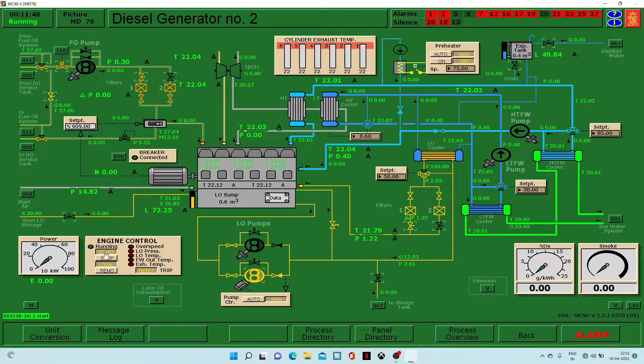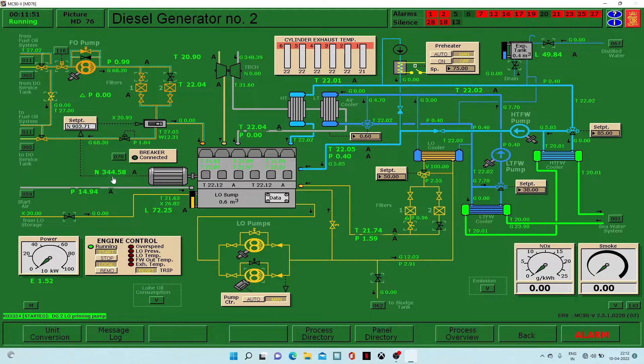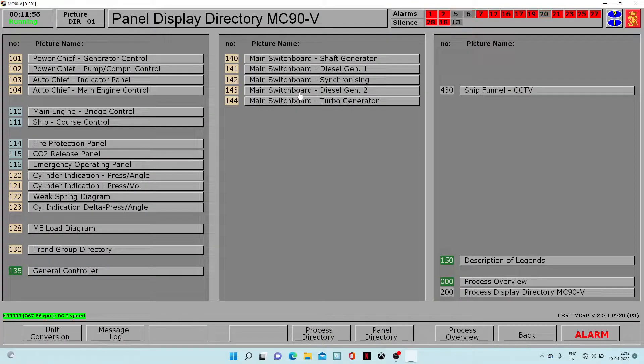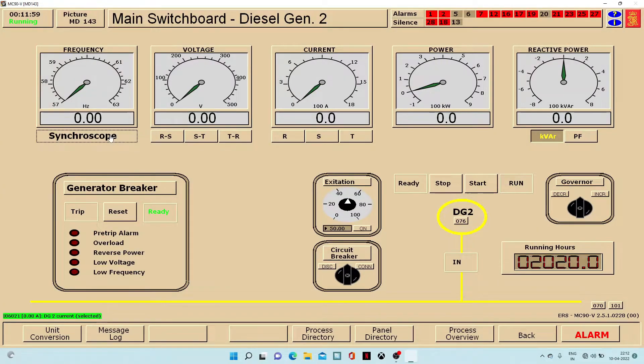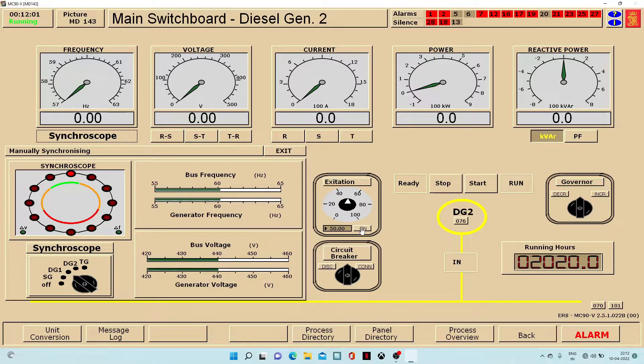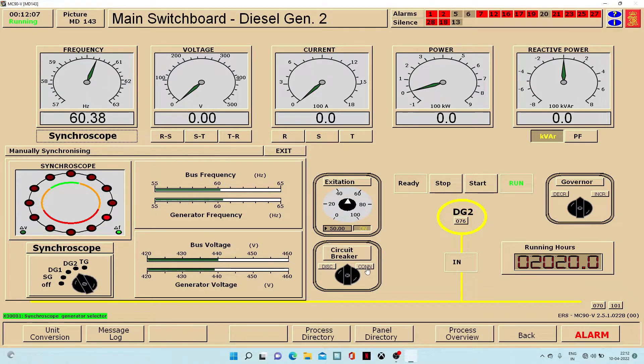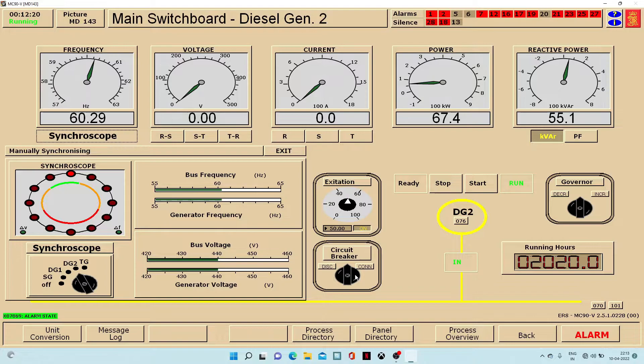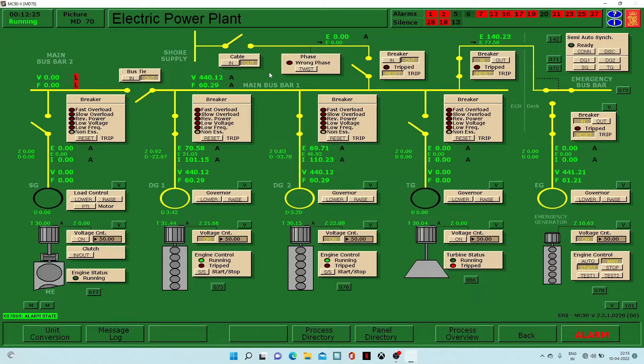We click on the start button for diesel generator two and it is taking RPM. Now we go for synchronizing — go to diesel generator two, click on the synchroscope, then click on excitation, then diesel generator two. We wait for the red color marking to come to the 11 o'clock position, then click connection, and it will stop at 12 o'clock. Our diesel generator two is now on load — both generators are running in parallel. We go to the electrical power plant to connect it to the bus bar.